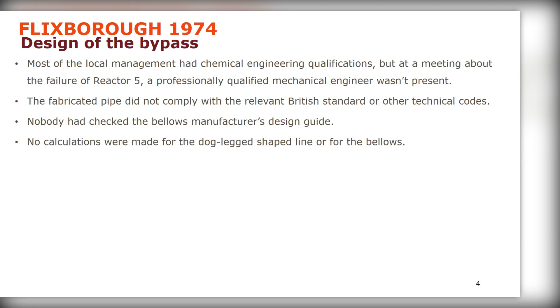Nobody on site appreciated that the bypass would be subject to turning moments and shear forces, which would be felt at the bellows. And if you know, bellows are designed to be linear in and out - they're not designed to twist.